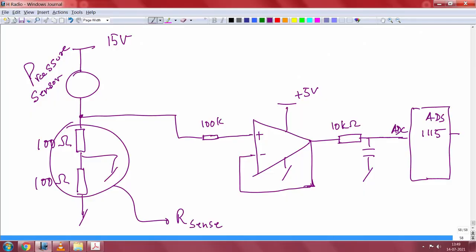For that, I will draw your attention to this circuit which we have done on the board. This is our familiar pressure sensor — I have applied 15 volts to it. It has just 2 wires: one goes to 15 volts, and the output current is measured through this resistor, which is the R-sense of the pressure transducer, and I will get some voltage from here.